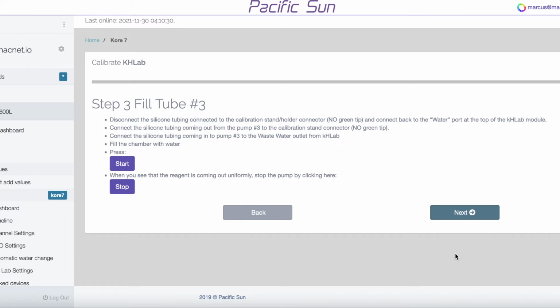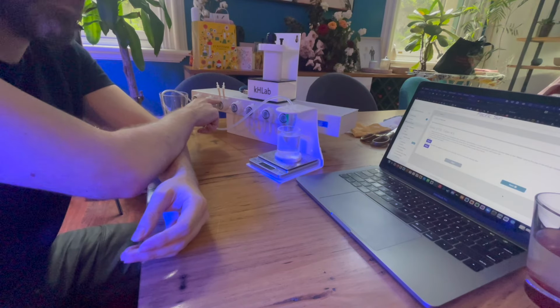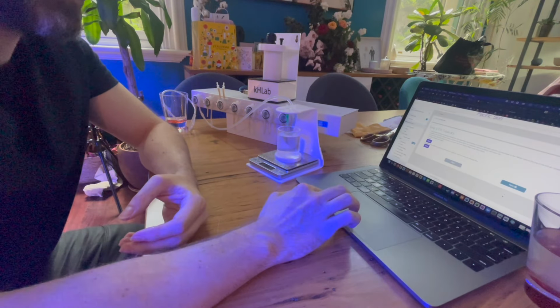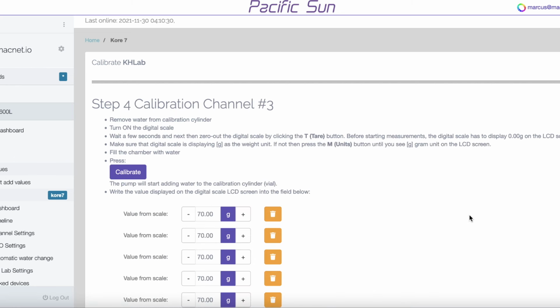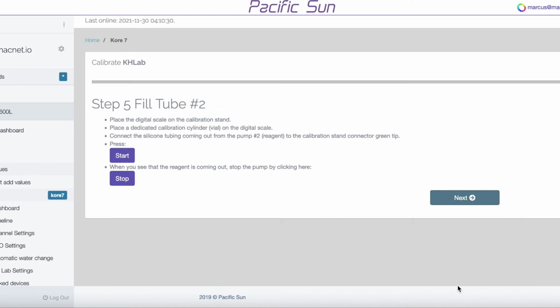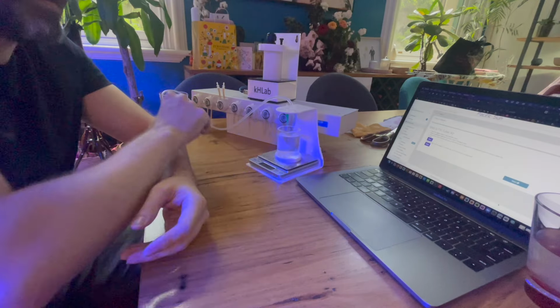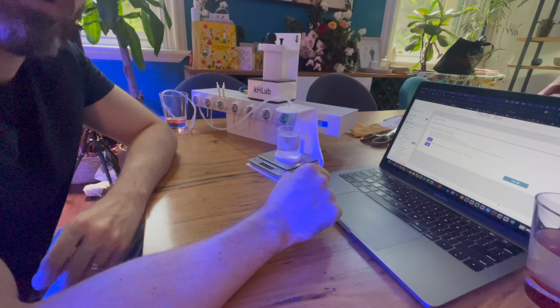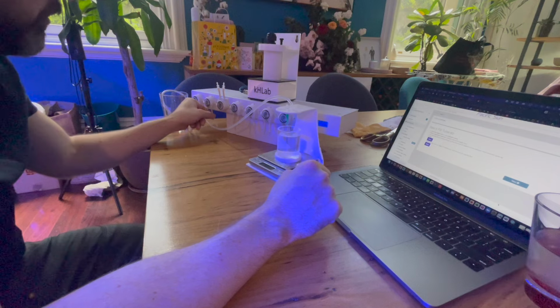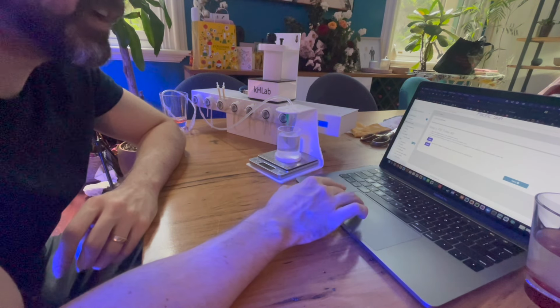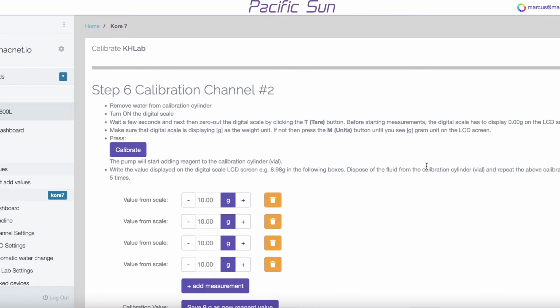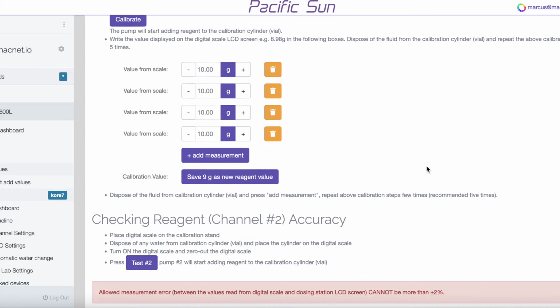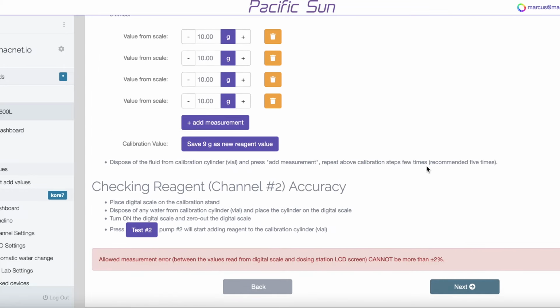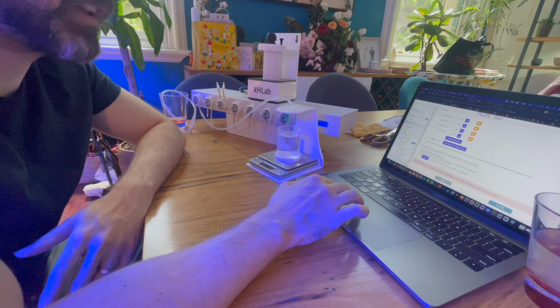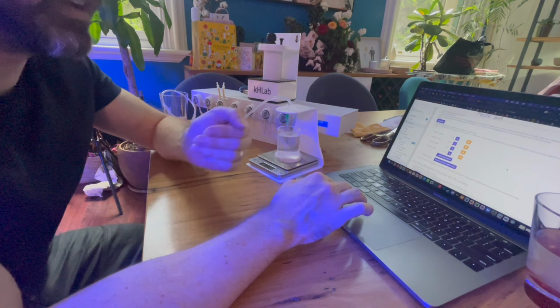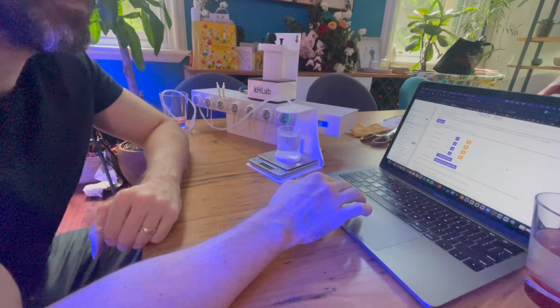The next one to do will be pump 3, which is the one here that I have upside down. That's for your wastewater. Once you've calibrated that, you'll then do pump 2, which is the reagent one here. That one's a little bit different. It's a slower pump with smaller tubing. So it won't be doing 70 mil. It'll be using 10 mil approximately for each calibration. But just follow the steps as written on the website and you should be good to go.